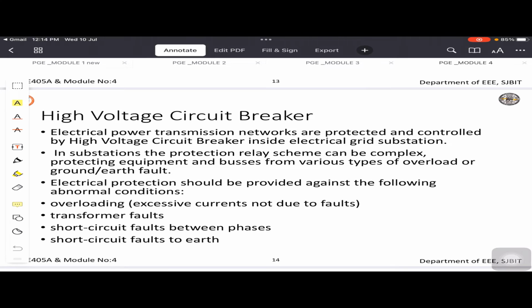Now, when a fault occurs on any part of the power system, the trip coils of the breaker get energized, or the moving contacts are pulled apart by some mechanism, thus opening the circuit. The separation of the current carrying contacts generally produces an arc, and the current is thus able to continue until the discharge ceases. This production of arc will delay the current interruption process, and it will also generate excessive heat, which sometimes may cause damage to the system, or the breaker itself might be damaged. Therefore, the main problem in the circuit breaker is the production of arc, which has to be extinguished within the shortest possible time, so that it does not heat up and affect the entire process.